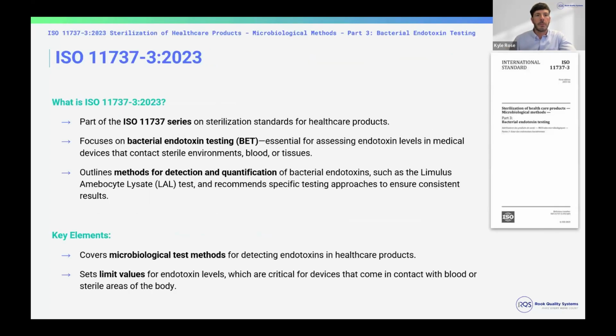First is the 11737. So this is the bacterial endotoxin testing. This is for assessing endotoxin levels in medical devices that are in a sterile environment that then contact blood or tissues. It outlines methods for detection and quantification of these endotoxins, such as the LAL test, and recommends specific testing approaches to ensure consistent results. This covers actual test methods, as well as limits for endotoxin levels for different types of devices, based on where they're contacting and how long they're being used.